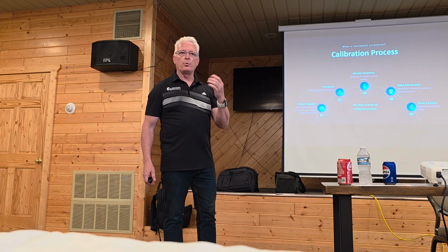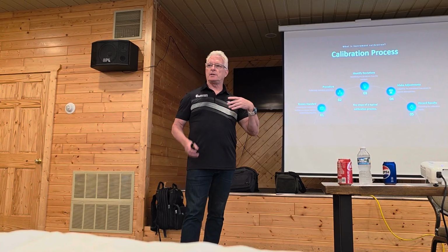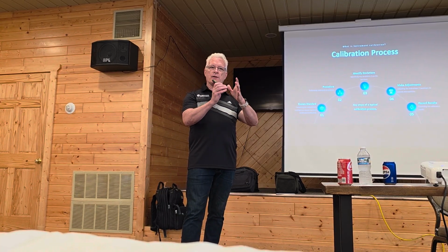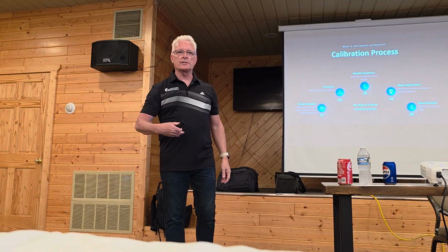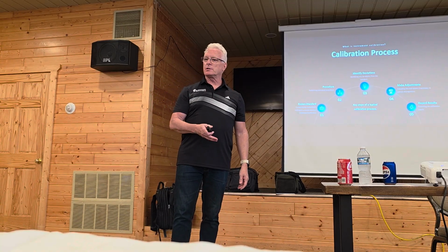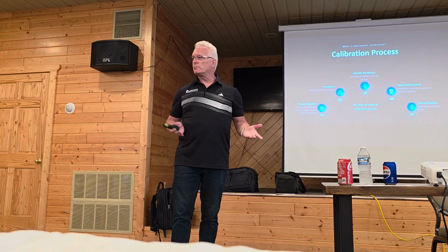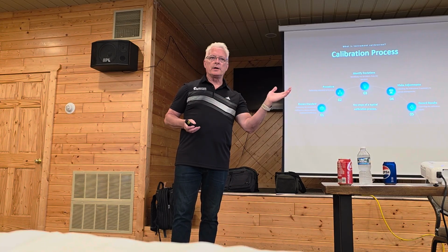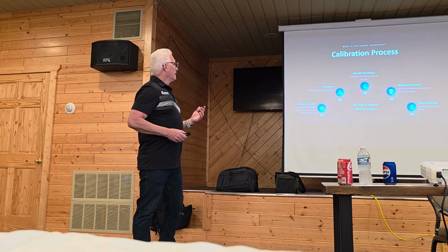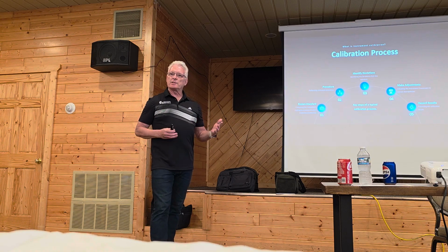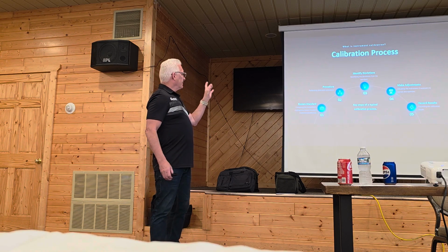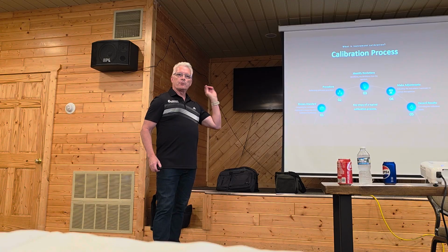Like a scale, you'd have a weight, and you have to know that it's a known standard so that when you step on the scale, you know it's accurate. Otherwise, if you have a comparative to something, it's called a reference, how do you know it's right? And that's the same with flow meters or whatever. Flow meters use verificators and different devices to do it. But the most important thing is that we have a known standard and we have a procedure to do it.